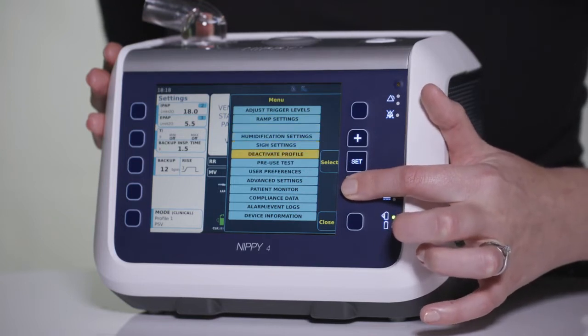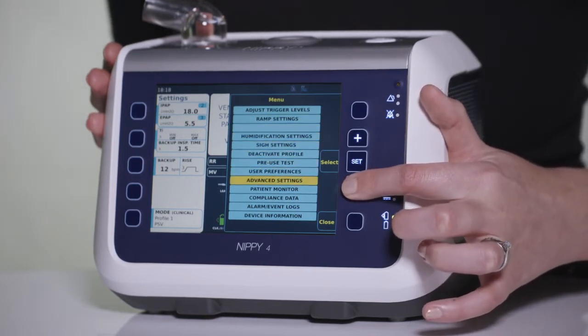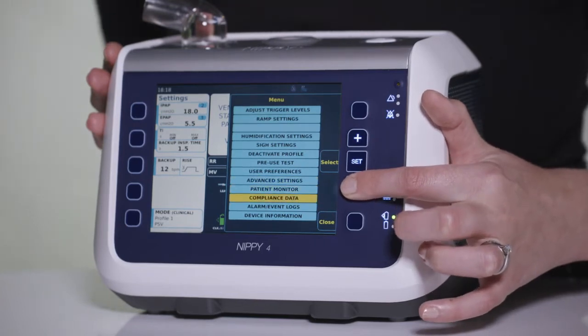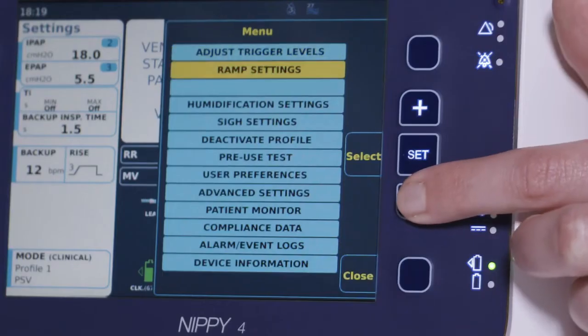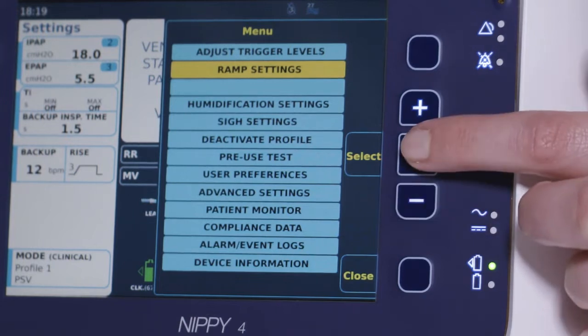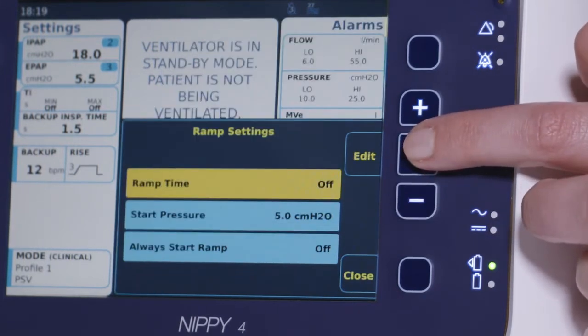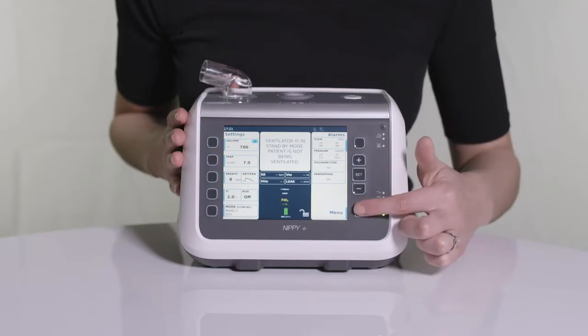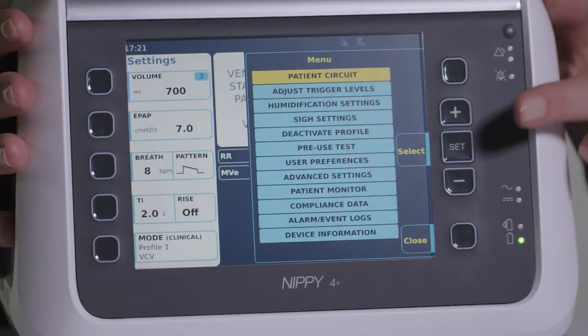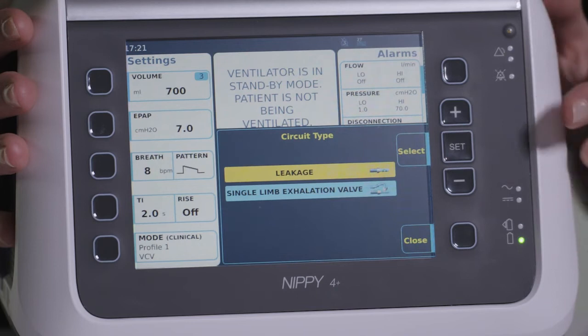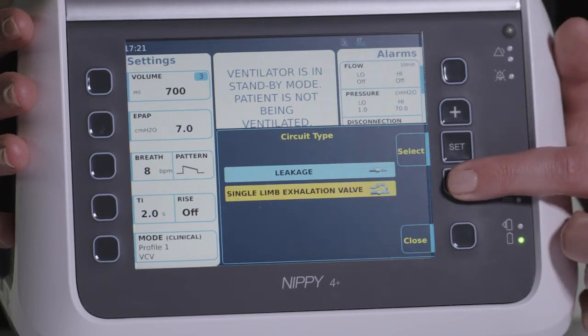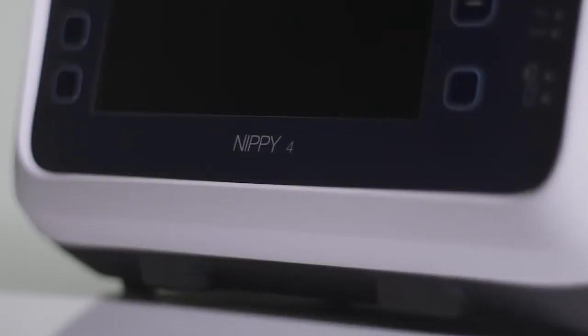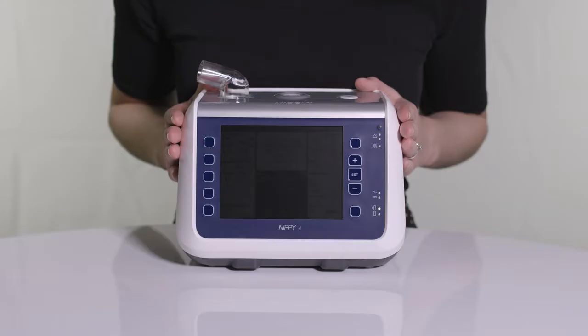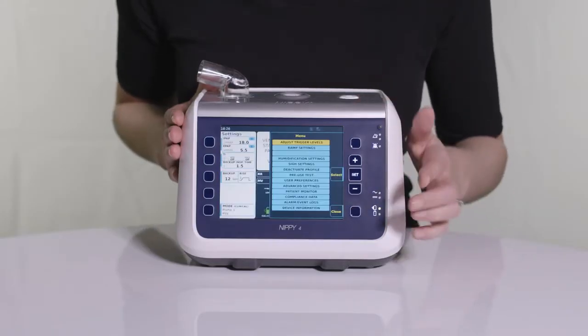To begin with, we should mention that there are some slight differences between the NIPPY 4 and the NIPPY 4 Plus menus. Firstly, the NIPPY 4 has an option to enable a ramp setting which you cannot do on the NIPPY 4 Plus. The NIPPY 4 Plus menu has an option to allow which type of patient circuit you wish to select, from either a leakage circuit or an active valve circuit. As the NIPPY 4 can only be used with a leakage circuit, this choice is not needed in the main menu. Let's walk through the rest of the main menu.